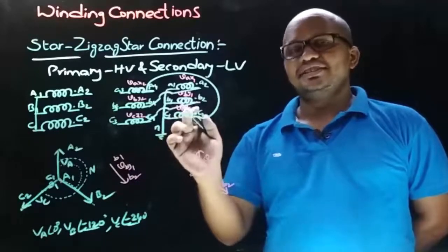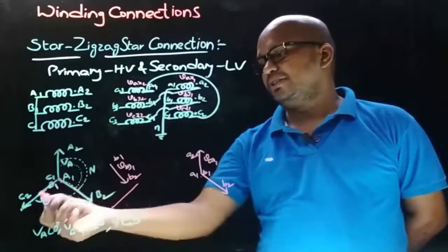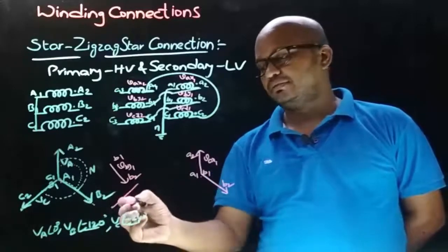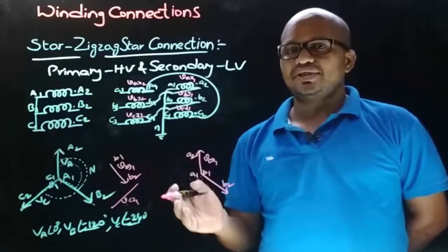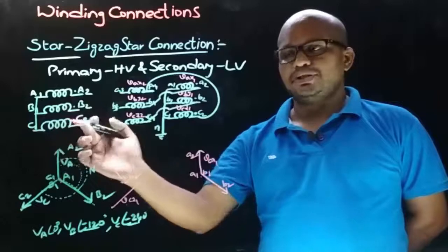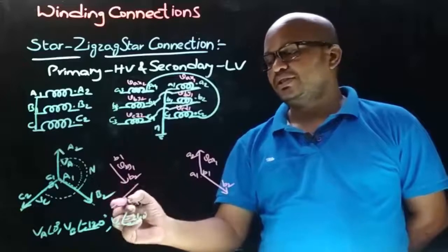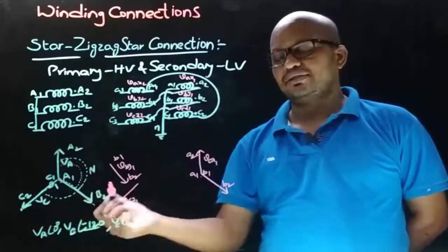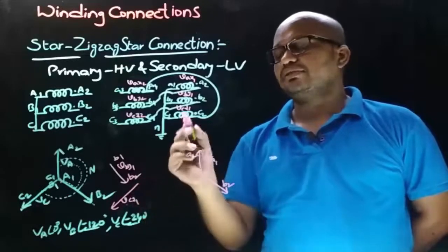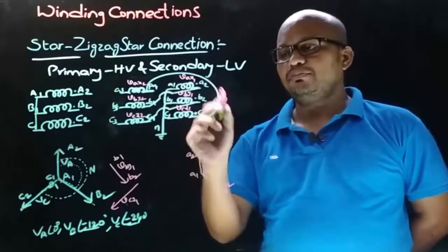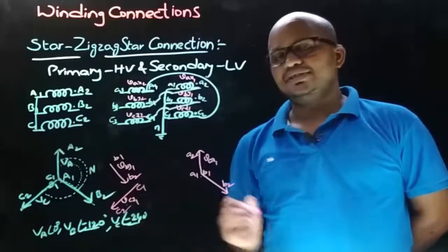Now let's draw the secondary side VCZ1 phasor. So let's draw the secondary side VCZ1 phasor parallel to primary side VC phasor somewhere here like this. This is VCZ1. And now we need to decide the direction of secondary side VCZ1 phasor. On primary side consists from dot end, and on secondary side consists from dot end. Therefore, direction of secondary side VCZ1 phasor is same to that of primary side VC phasor. So like this. Now we need to decide the terminals of this secondary side VCZ1 phasor. So terminals are C1 and C2, and they consist from dot end terminal, that is C2. Therefore, arrow end will be C2 and other end will be C1.